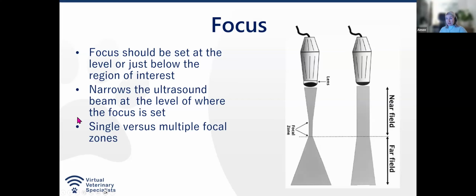So next one is our focus. And that's usually indicated along the side of our image with a little arrow, a little asterisk sometimes. Again, there can be various things down the side of your image, okay? Just learn what they are on your image. The focus narrows the ultrasound beam at the level of where it's set, okay? So it increases the line density there, so you get better image resolution. So we want to set that focus at the level of what we're looking at or just below it, okay? So therefore we get better resolution at the area of interest.